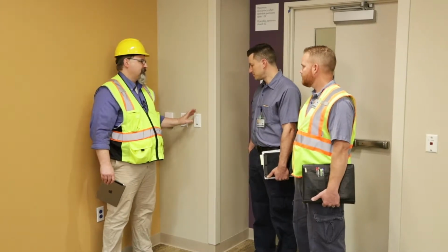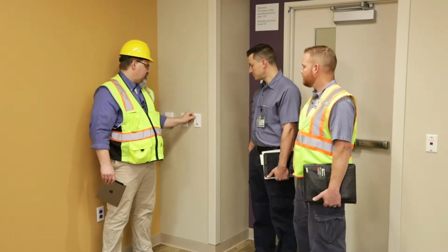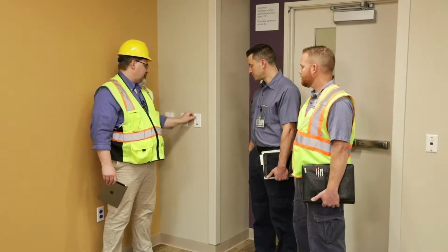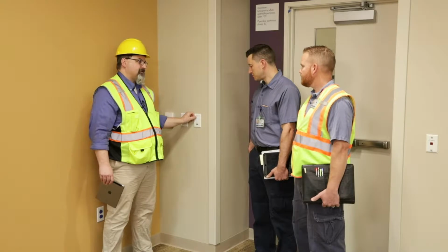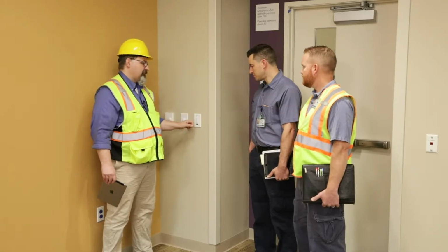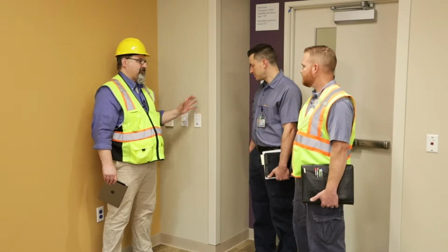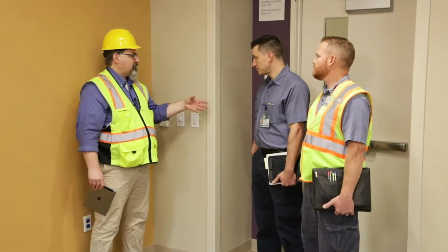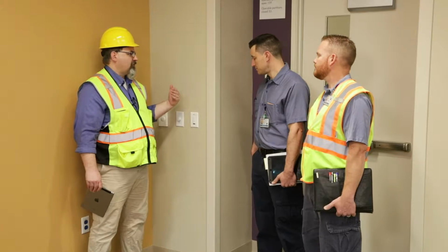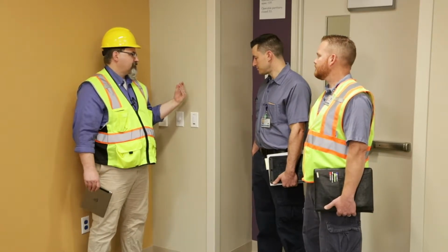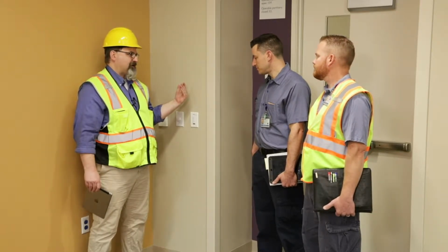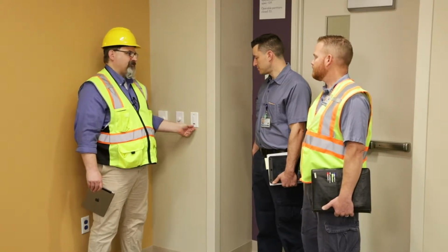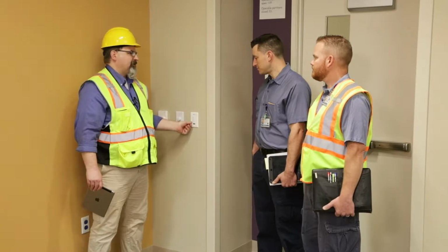Most of the buildings use 0 to 10 volt dimming. And so when you dim things, you press and hold and it lowers the lights, and you press and hold and it raises the lights if there's dimming fixtures in there. Now there are a couple of situations where we had dimming switches and non-dimming loads. You guys will have the cut sheets and the drawings to look up what fixture you had in that space, and you'll know that it's dimming or non-dimming. You'll be able to tell us, hey, I've got a dimming fixture, but it's not dimming, what's my problem?